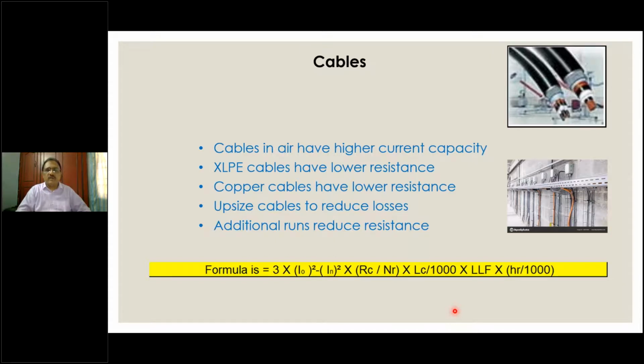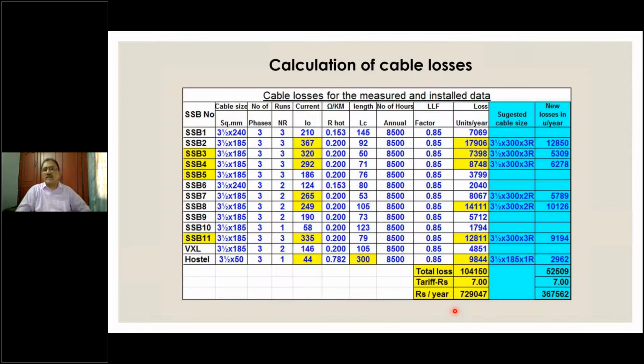With this, you can be able to calculate the losses in the network, in the cable system. Apart from selecting cables for the voltage drop, short circuit current, and things like that, you can also make selection of cables for the losses in the network. So I will explain through one slide here. This is a textile industry, where upsizing is typically practiced by all the leading electrical engineers. They will not choose anything less than 300 or 400 square mm. But this one particular industry did not probably have the wisdom of the same experience.